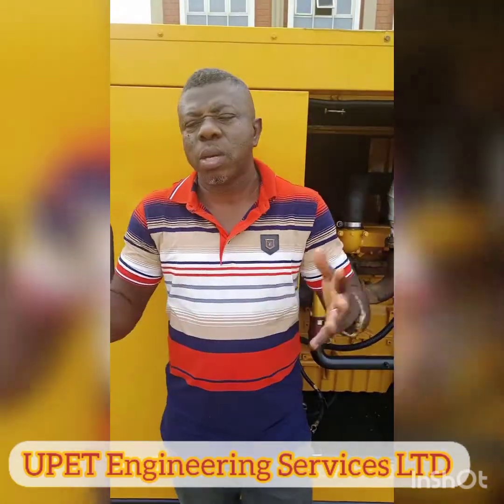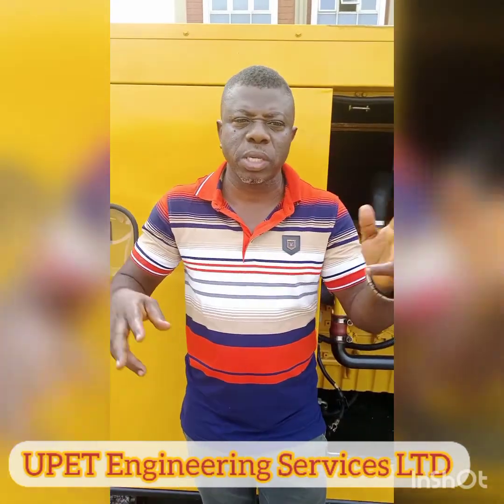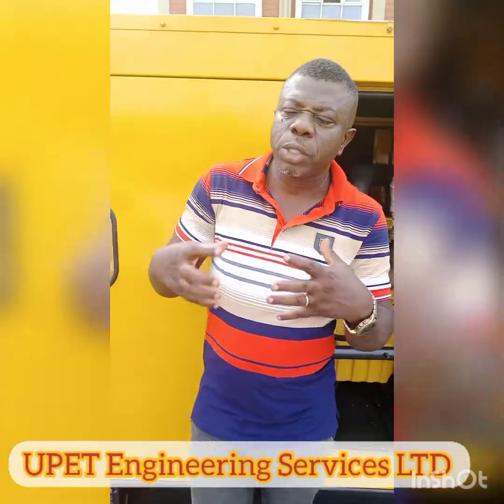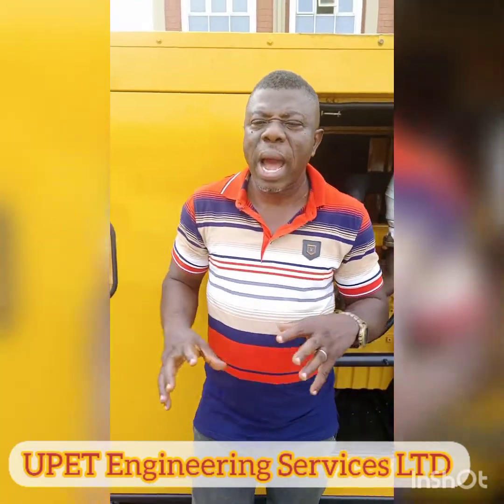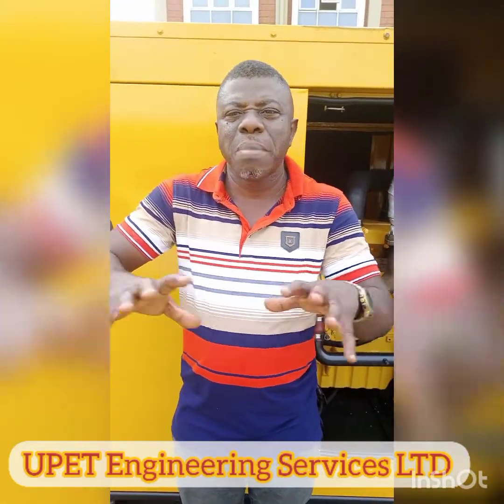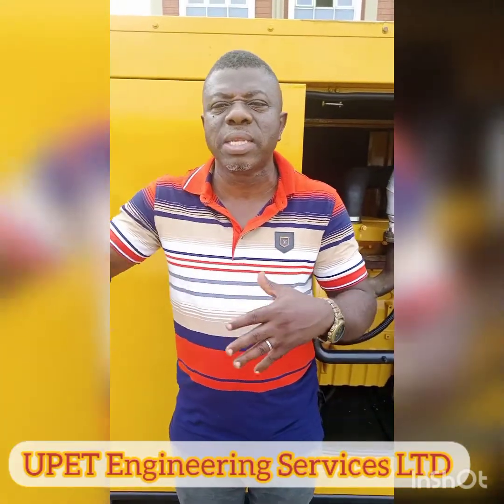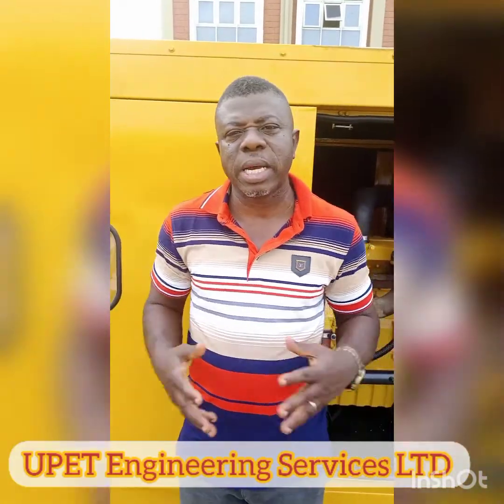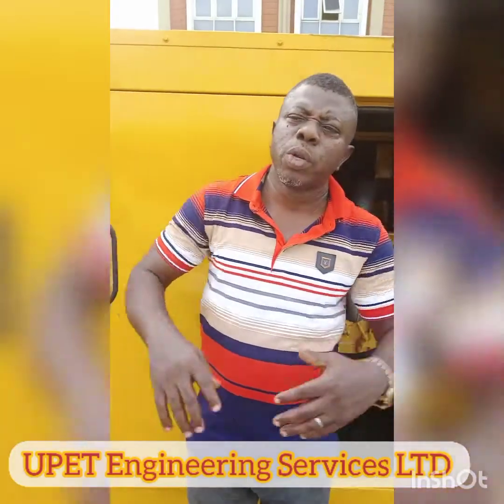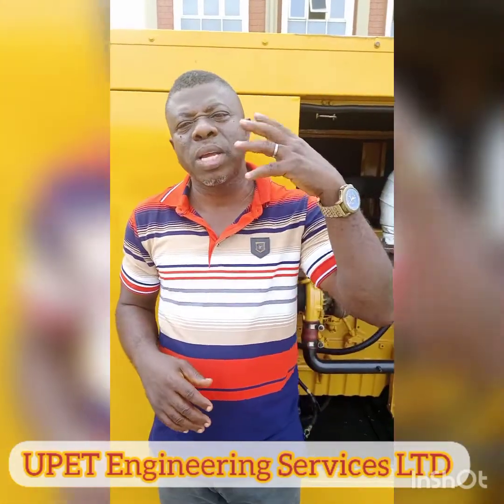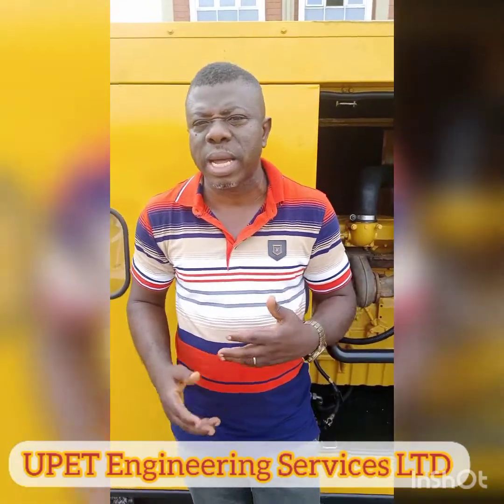But in most cases nowadays, some engineers or technicians, once a generator is shutting down, will go and start cutting all the wires of the sensor because they don't know where the problem is coming from. But the manufacturers place those sensors there in order for the generator to shut down in an emergency without causing any damage to the genset. But the technicians of nowadays no longer follow due process. So anytime anybody is maintaining your genset, ensure that they don't tamper with the sensors, because sometimes that sensor might be bad and it's shutting down. You can just spend about 10,000 to 15,000 naira to replace that sensor.